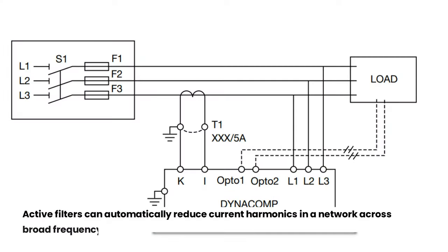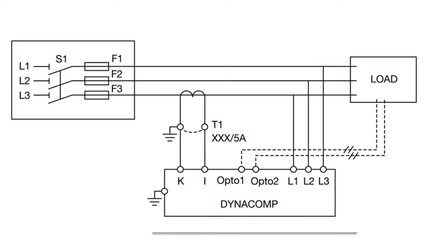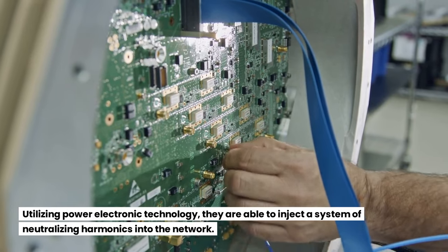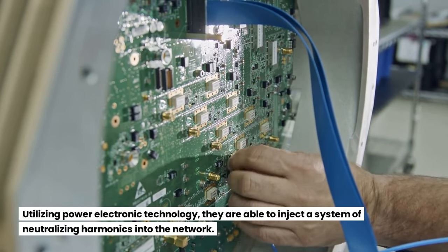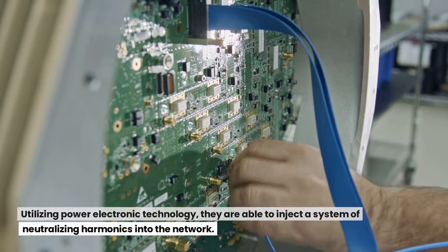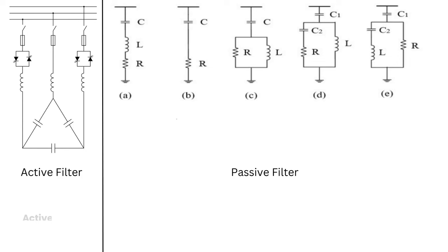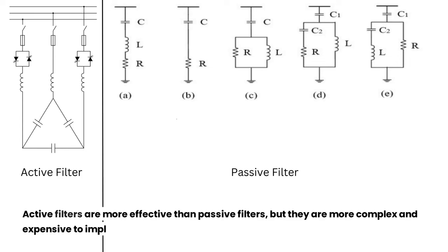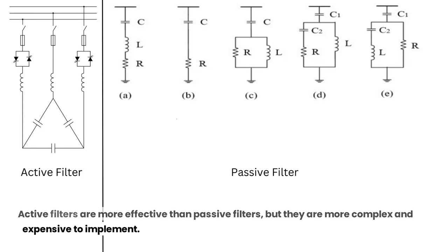Active filters can automatically reduce current harmonics in a network across a broad frequency spectrum. Utilizing power electronic technology, they are able to inject a system of neutralizing harmonics into the network. Active filters are more effective than passive filters, but they are more complex and expensive to implement.